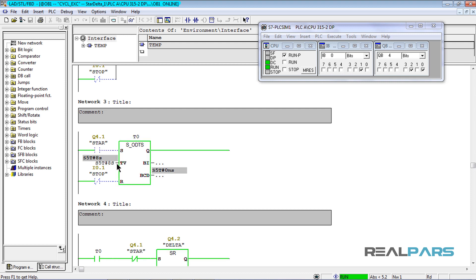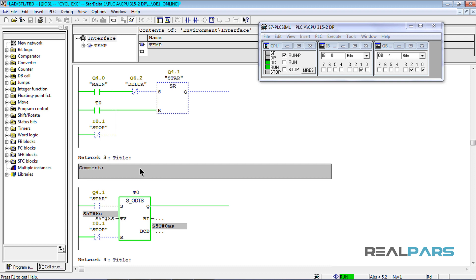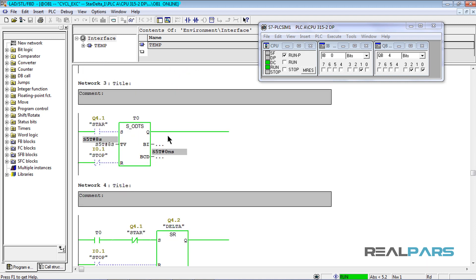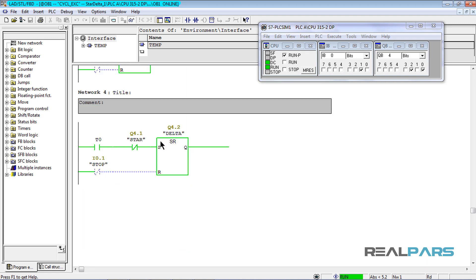After 8 seconds, when the timer is active, this open contact will be true and de-energize the star contactor. At the same time, since the timer is now active and the star contactor is de-energized, the delta contactor is going to be energized in the last network.